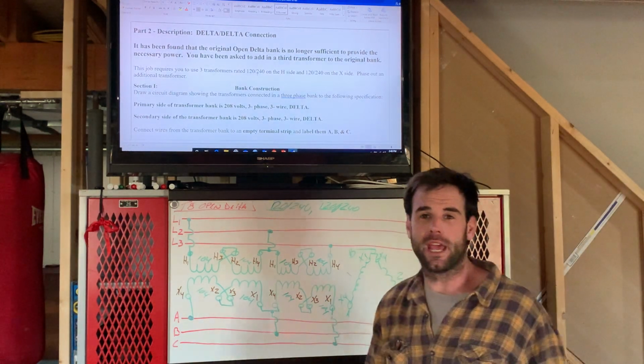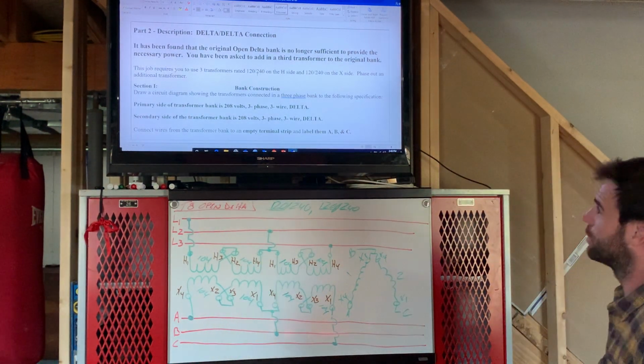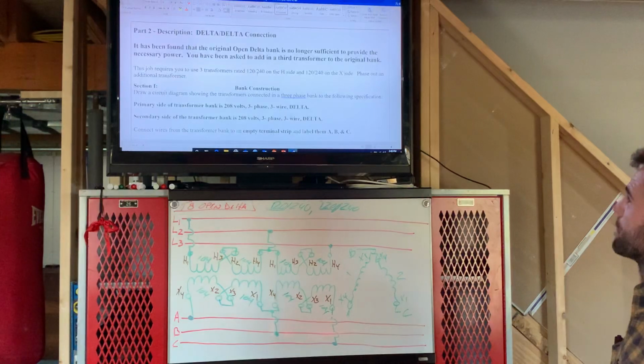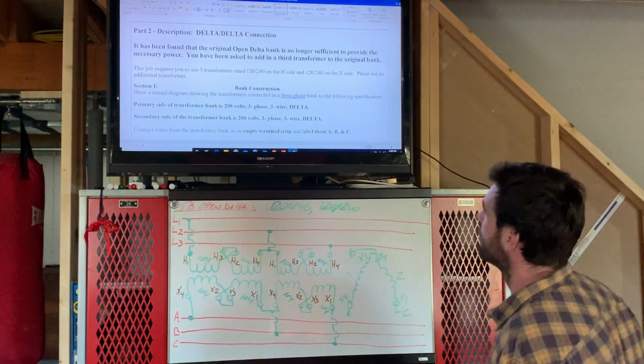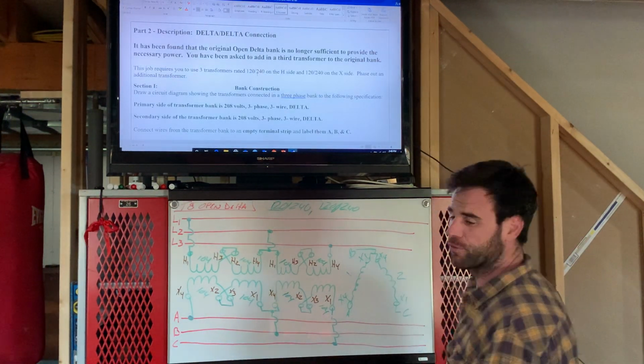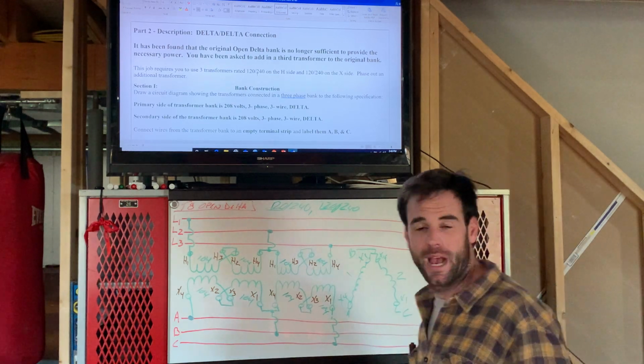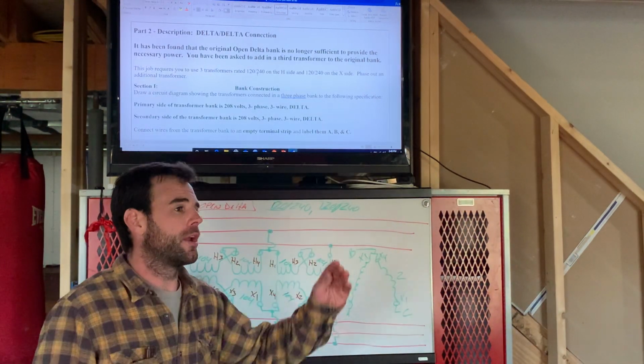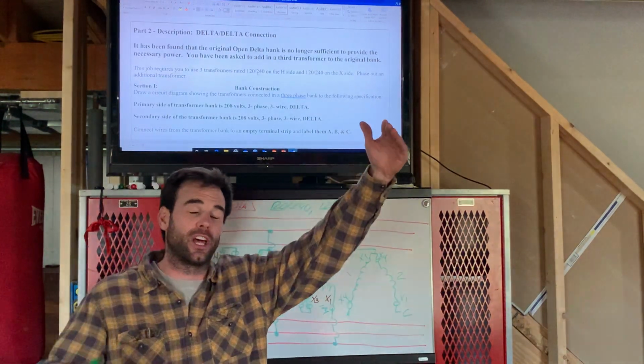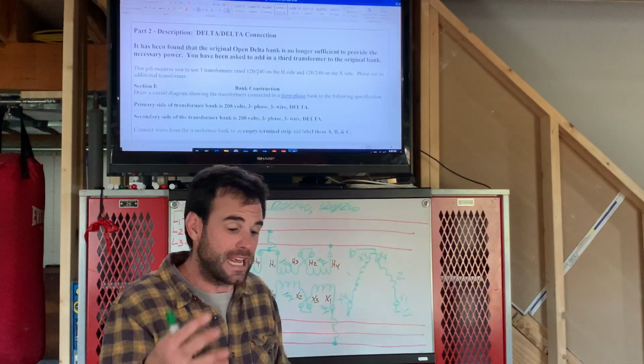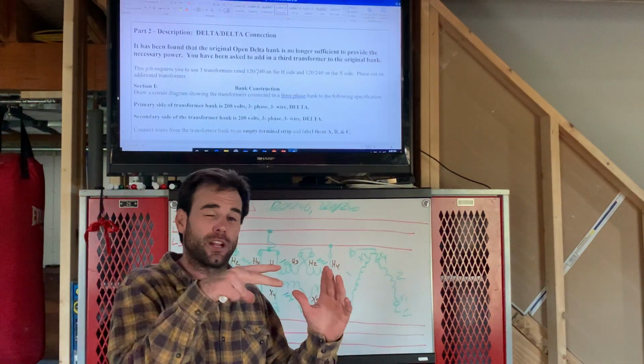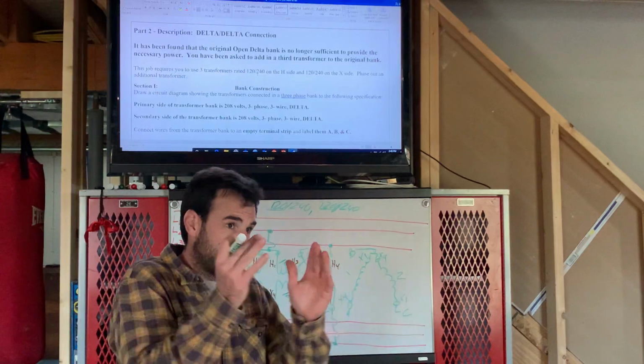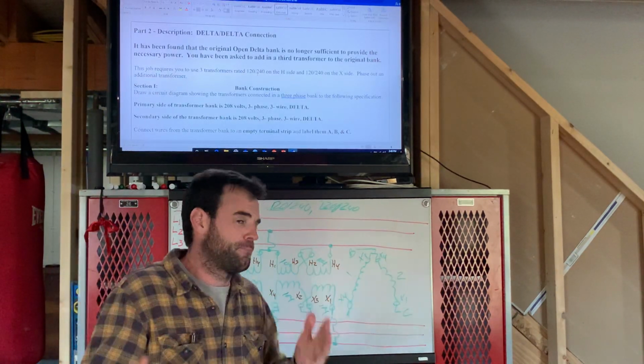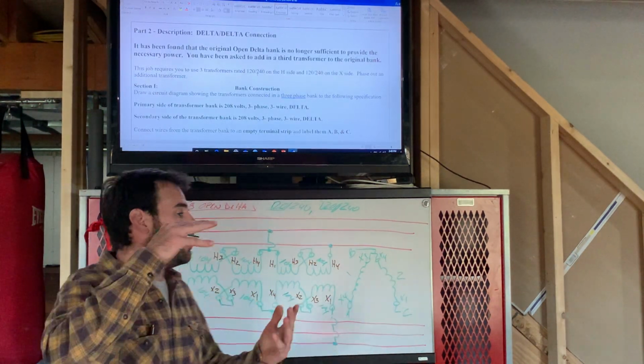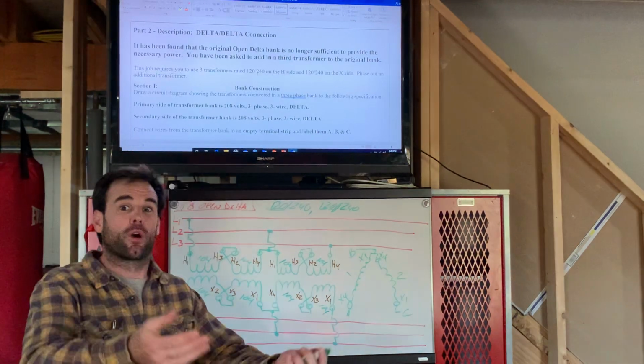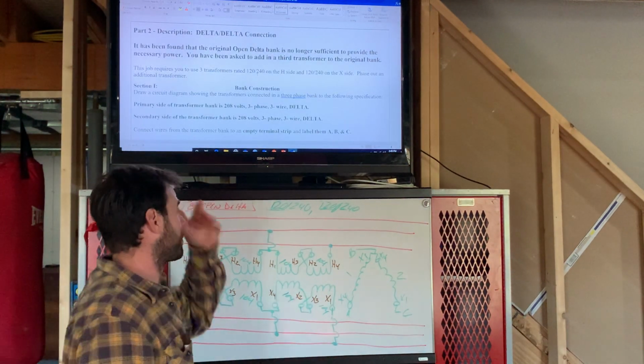So now what they're saying is, it's been found that the original open delta bank is no longer sufficient to provide the necessary power. You have been asked to add a 3rd transformer to the original bank. So we operated on an open delta. We have now gone past our kVA capacity, just like in job 4, in T4, how we had to put the 2nd transformer in parallel with the 1st to increase our kVA capacity. Same concept here. Our business has grown. We need more power. We need a bigger transformer bank.